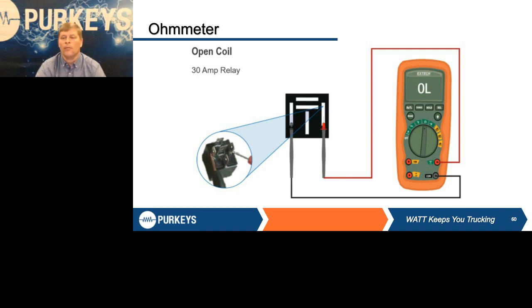and that relay coil cannot work. This also goes back to make sure you got your meter set on the right setting. If you had this thing, say, turned on the 200 ohm scale or 2 ohm scale or whatever, and you had it on the wrong one, and it didn't allow it to go up high enough, could you easily condemn a perfectly good relay? Yes. So again, make sure you do have your meter on the right function and the right scale.